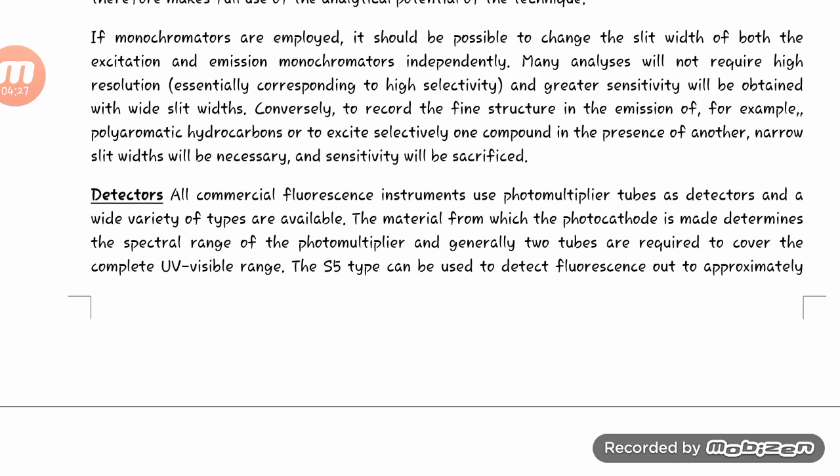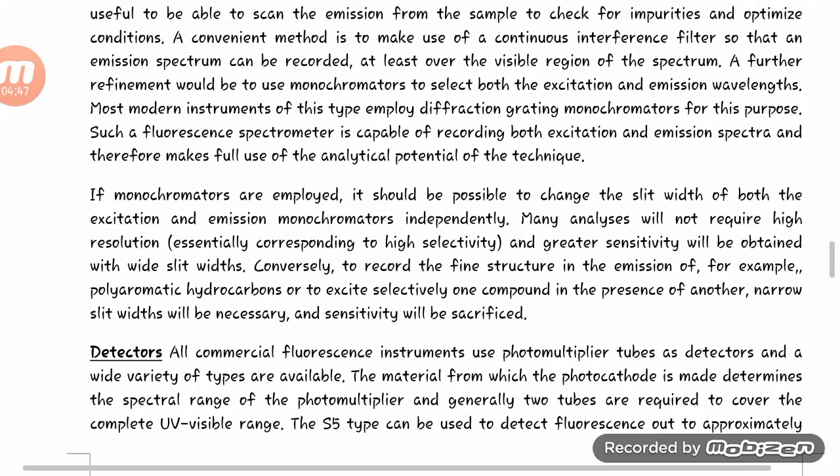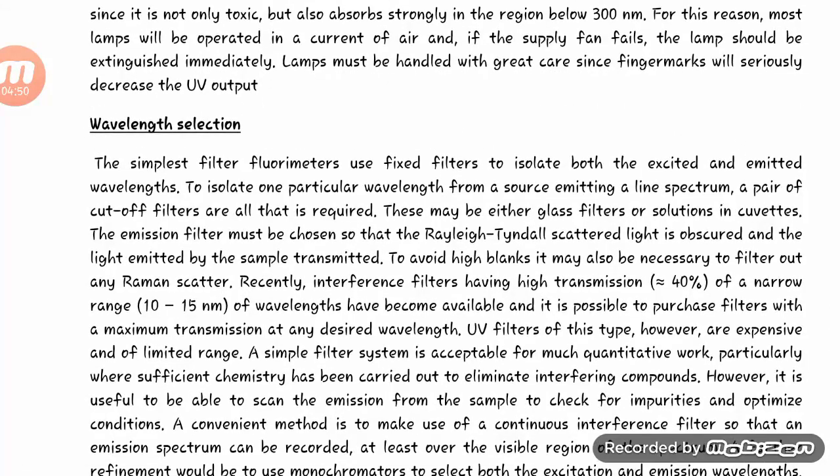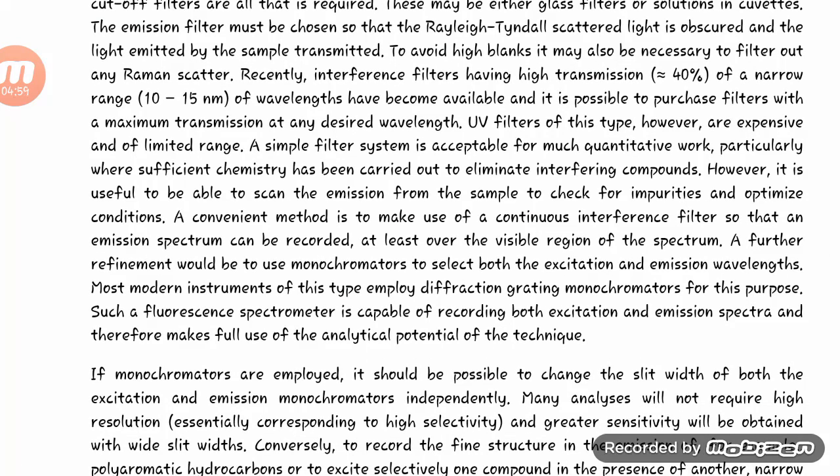Conversely, to record the fine structure in the emission of, for example, polyaromatic hydrocarbons, or to excite selectively one compound in the presence of another, narrow slit widths will be necessary and sensitivity will be sacrificed. So, by this, we can select the wavelength for fluorometry.